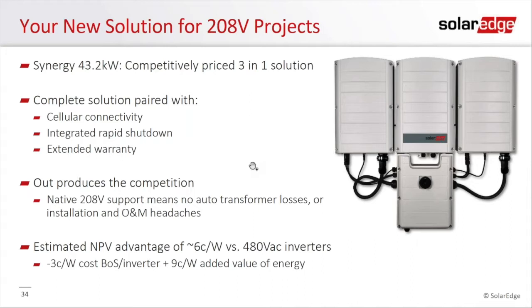And then when you add the turnkey offering that SolarEdge brings to the table, whether it's cellular connectivity, the integrated rapid shutdown, where we work so seamlessly and so nicely on rooftop projects, and extended warranty costs that are very, very low. And on the revenue side, we are able to outproduce the competition because of the optimizer, the power point tracker at the module, and the fact that we're native 208 volts, eliminating any need for transformers, installation costs, and O&M headaches related to putting in a step-down transformer. As we've shown in the project analysis, the production benefits and the overall cost benefit of using this native 208 inverter really make your project competitive, and give you a good alternative to other solutions on the market that may not give the same value that SolarEdge brings to the table.